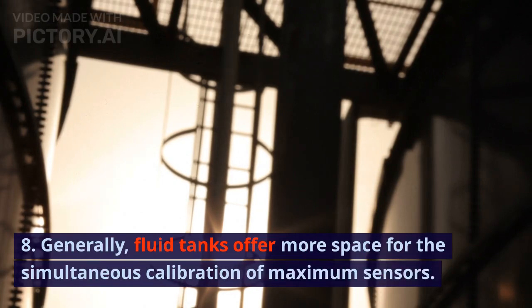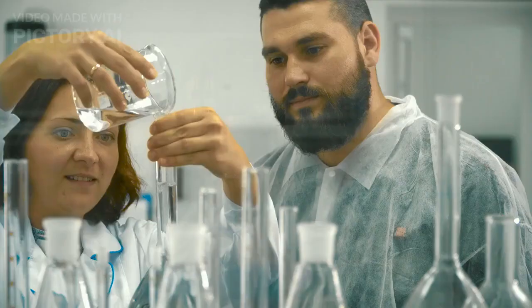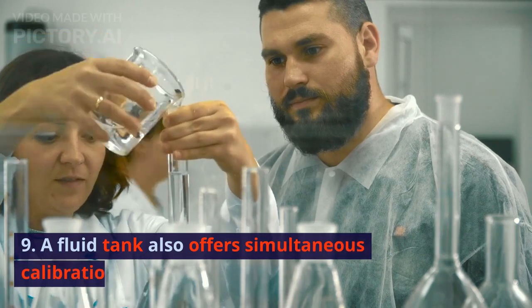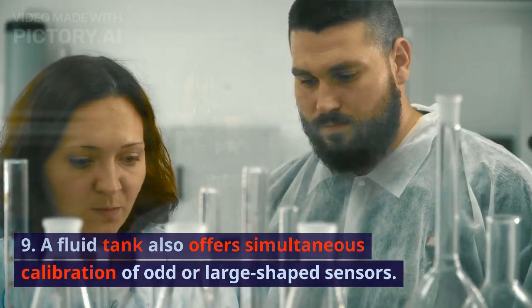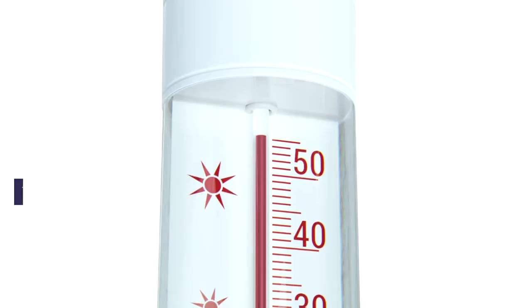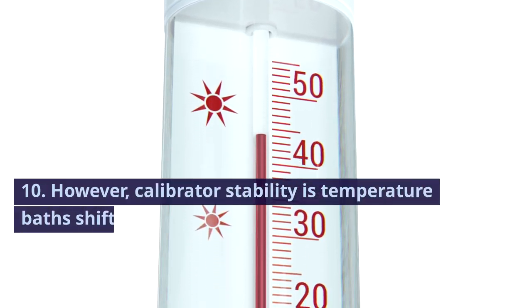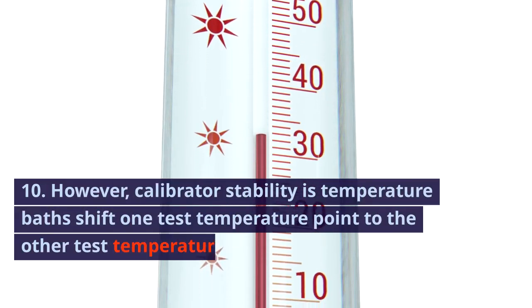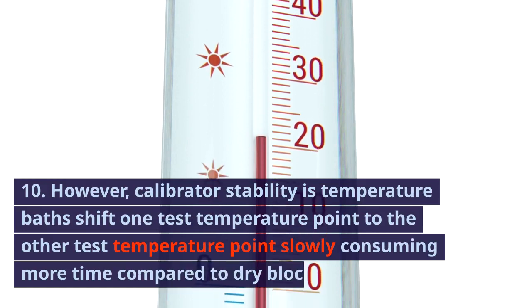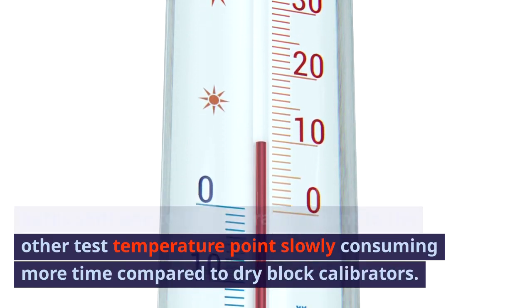Generally, fluid tanks offer more space for the simultaneous calibration of the maximum number of sensors. 9. A fluid tank also offers simultaneous calibration of odd or large-shaped sensors. 10. However, temperature baths shift from one test temperature point to the other slowly, consuming more time compared to dry block calibrators.